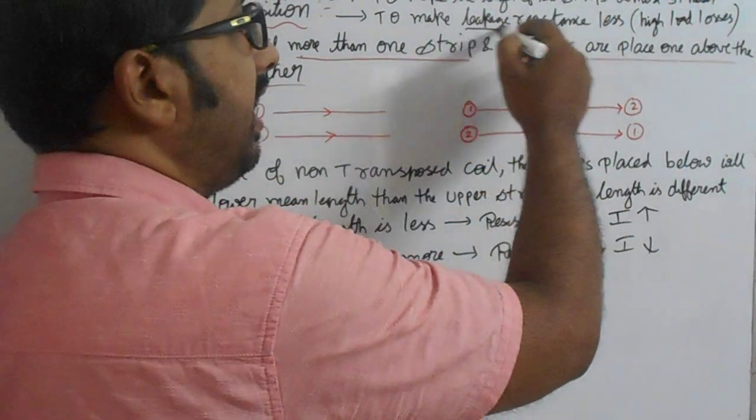If you see the upper one, the mean length will be more, the resistance will be more, and the current will be less. So uneven distribution of current will lead to more load losses or high leakage reactance.